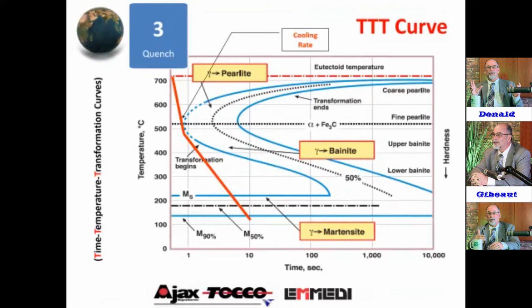But our quench is a series of small holes that make up a wall of water that is just pounding this thing. There are others that have big openings and they flood quench at a single point of impingement, and it deflects up, and then you have another one and another point of impingement. But if you do a thermal video, which I have, looking at that design, you can watch the temperature creep back up in between these points of impingement. And the argument was that we have real fine holes and there's scale in the system, and that could clog it.